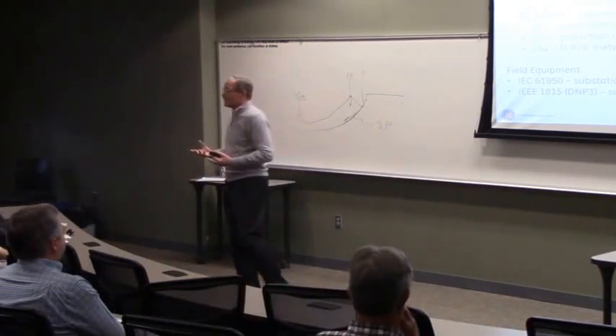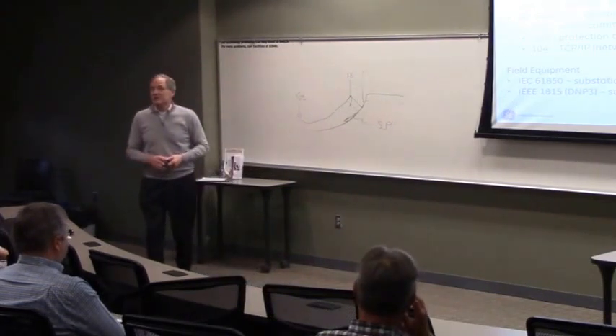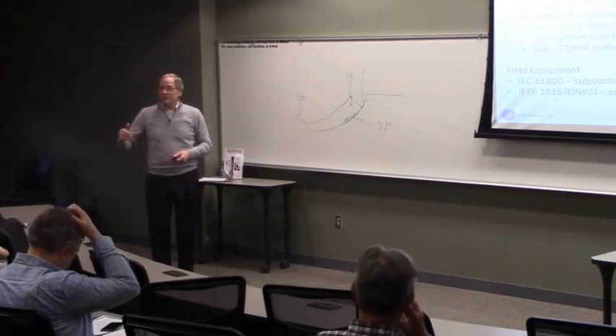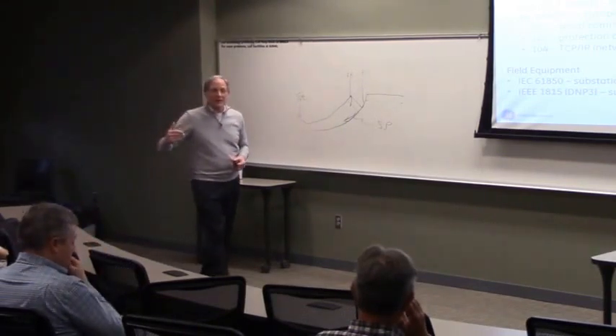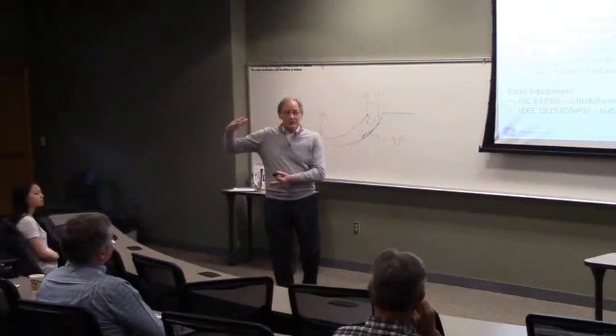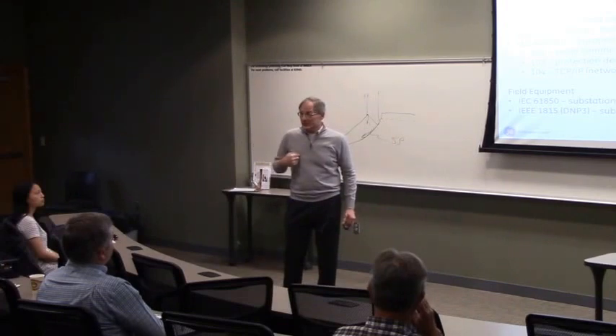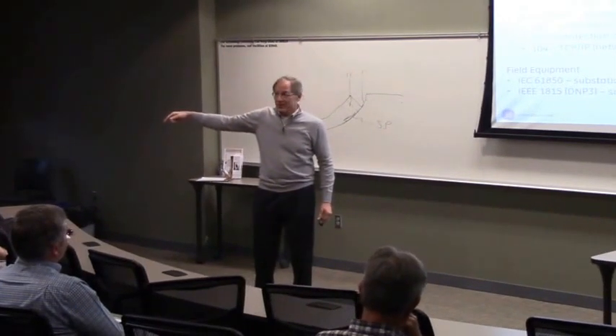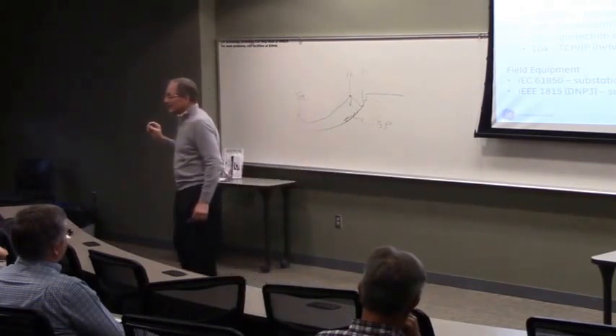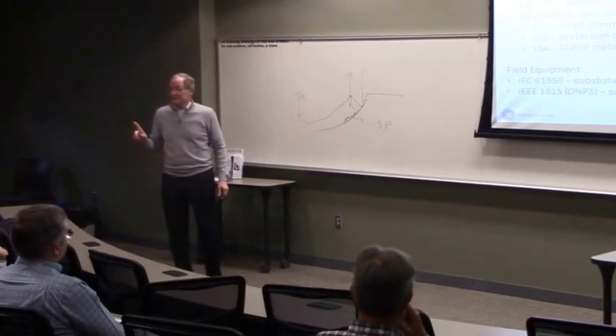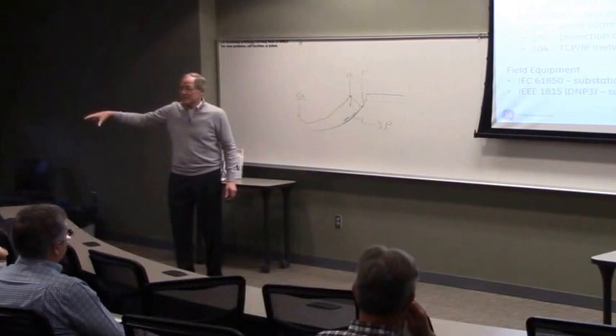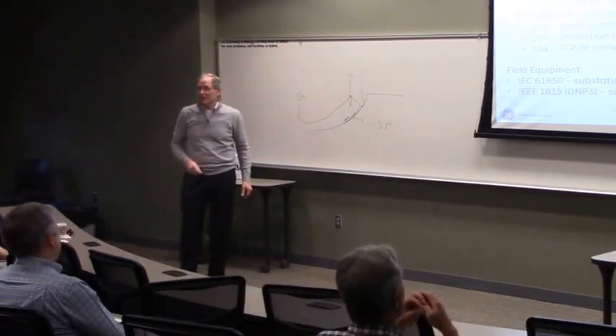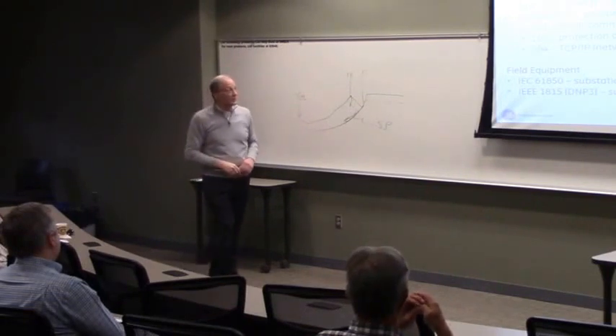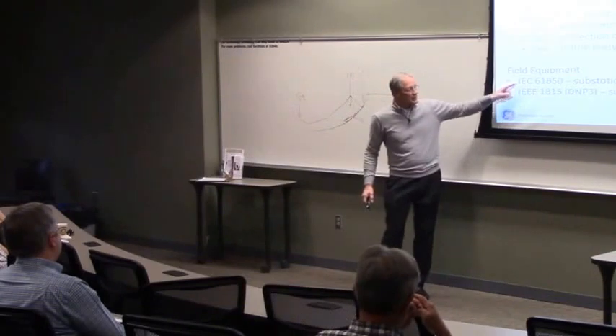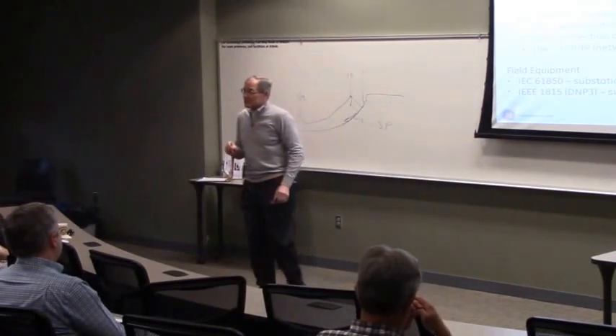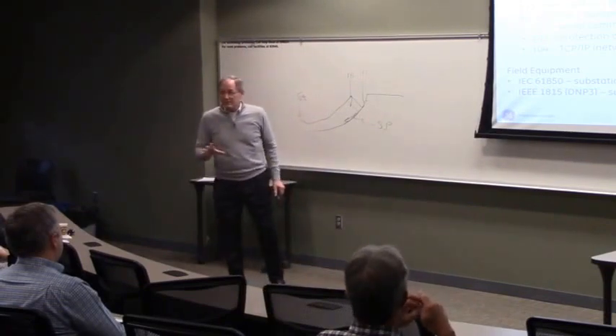If you're in a utility and you're going out for bid for a substation data concentrator, you can say in your procurement spec that your proposal must include a certificate that the equipment you're proposing has been tested by one of these independent companies, that the DNP protocol has been accurately implemented in your product per the standard, and that the company that did the testing was approved by the user group of the protocol. The same is true for IEC 61850 in the substation. That's called the UCA International User Group. And again, the same thing occurs.